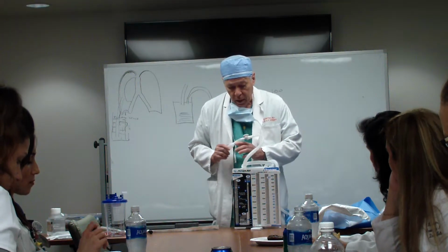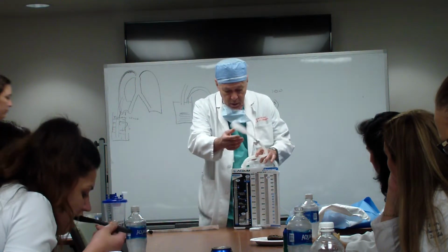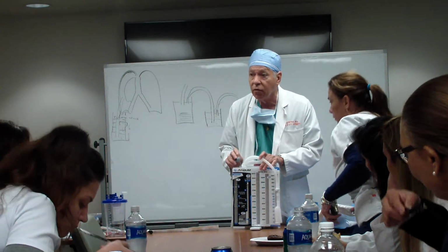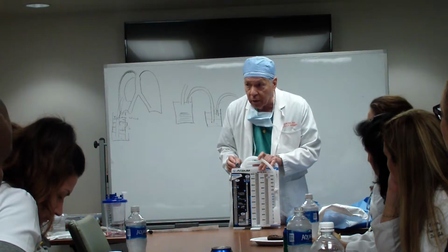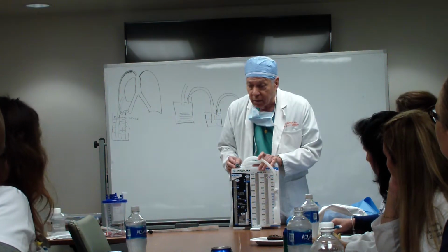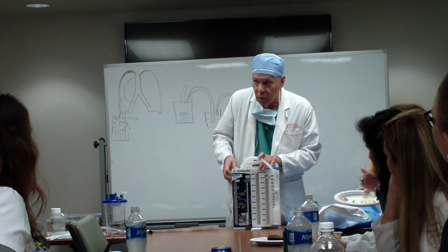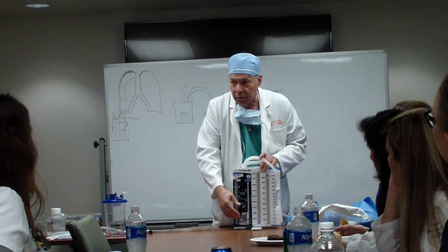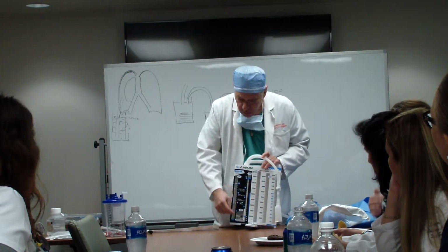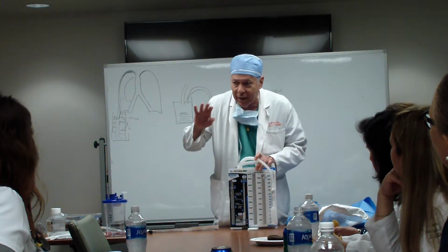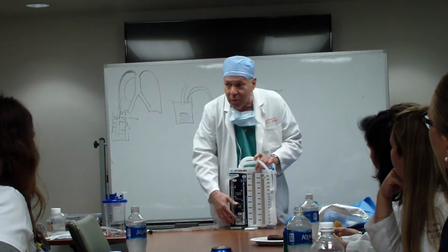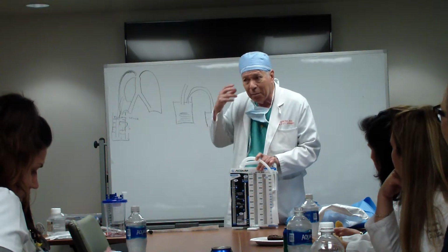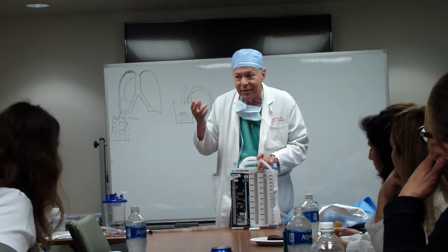This device here has only one function. This is a muffle, to muffle the noise of the bubbling. And when you put suction in the wall, put enough until it starts bubbling, until you have bubbling here. Don't put any more, because you can put 200. That is not going to be more than 20 centimeters by the physical law that I explained to you. And it can be annoying for the patient, all this horrible noise. This little amount of noise doesn't bother the patient.